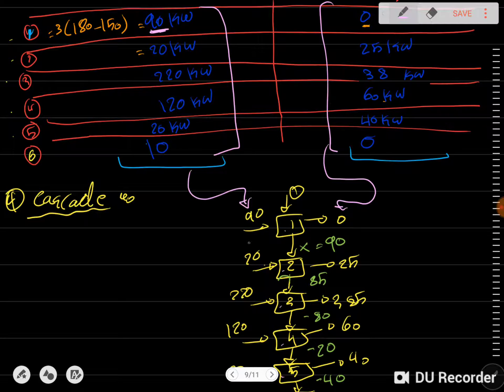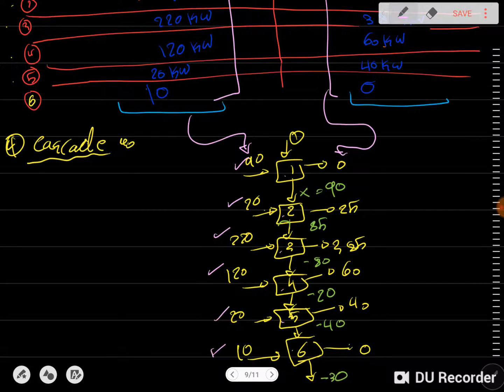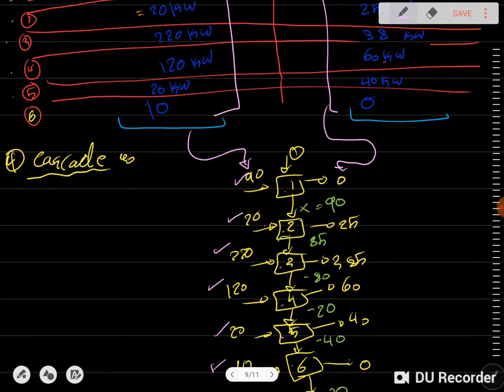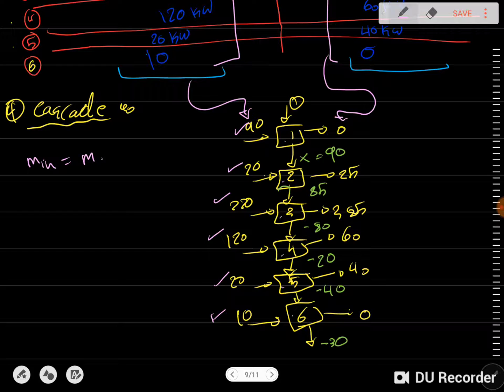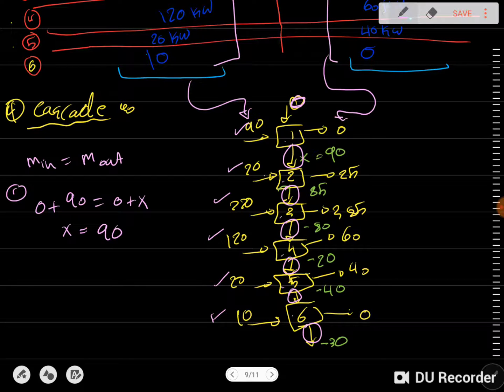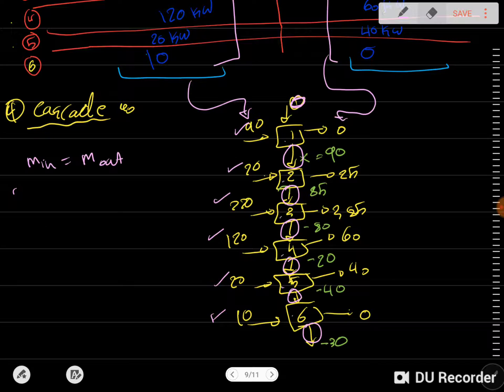The hot summation values for the six intervals are 90, 20, 220, 120, 20, and 10. We then apply a rule similar to mass in equals mass out. For the first interval: 0 plus 90 equals 0 plus x, where x is the residual — the arrows coming out of each box. So x equals 90. We calculate the residual for all intervals in the same way.